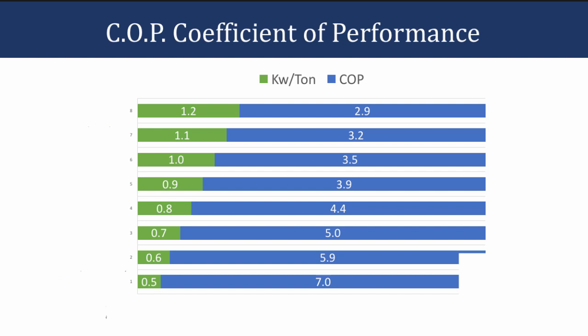These two metrics go hand in hand. On the bottom of this chart, the green numbers are the KW per ton — the smaller the KW per ton number, the more efficient the equipment or central plant. For COP, the larger the number, the more efficient the equipment. A large, inefficient KW per ton is equivalent to a small, inefficient COP. As the KW per ton gets smaller, the COP gets larger. You want to be towards the bottom of the chart — that's the more efficient range.